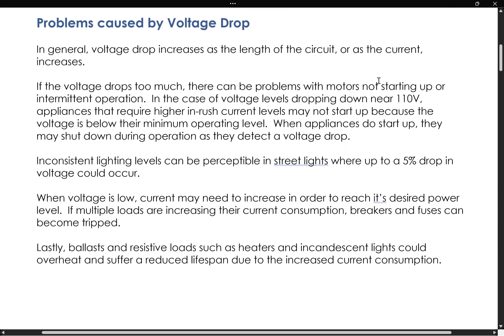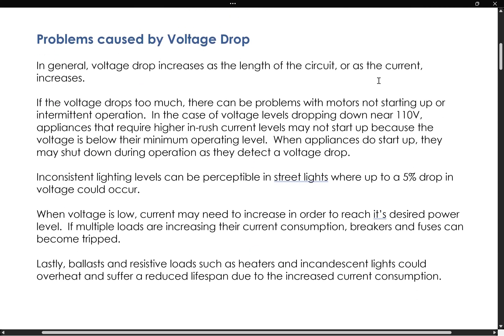So why is this a problem? Voltage drop is a problem for a lot of reasons. As the voltage drops, there's less voltage and the current is going to increase. If it drops too much, there's going to be problems with appliances because of their motors — they're going to not start up, or they're going to have intermittent operation. If voltage levels drop near 110 volts, appliances that require a high inrush of current may not start up because their voltage is below their minimum operating level.